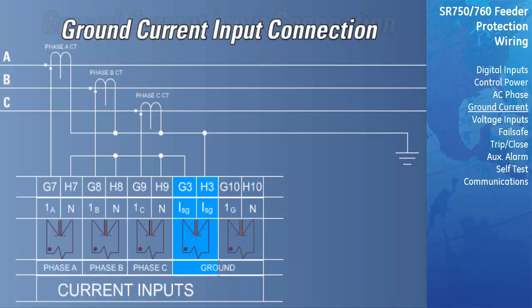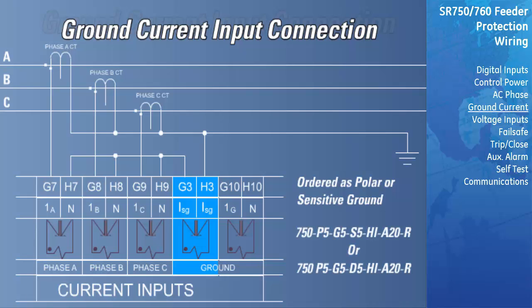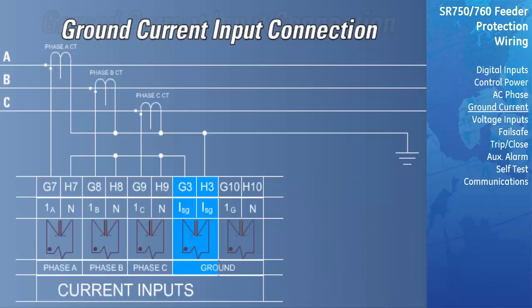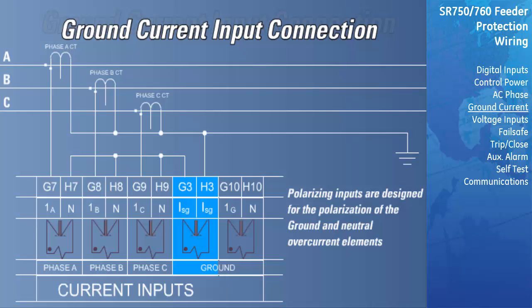The G3H3 ground connection can be ordered as a polarizing ground connection or sensitive ground connection. The relay order code will indicate which ground connection is installed in the relay. An S5 indicates a sensitive ground, while a D5 in the order code indicates a polar ground connection. The sensitive ground is intended for high impedance grounded systems or ungrounded systems. The maximum fault current must not exceed 500 amps. The polar ground is used to set the reference for ground and neutral directional overcurrent. If the relay does not have this option, a phase voltage reference will be used for the directional elements. There are three methods for connecting the ground inputs of the relay to the system.